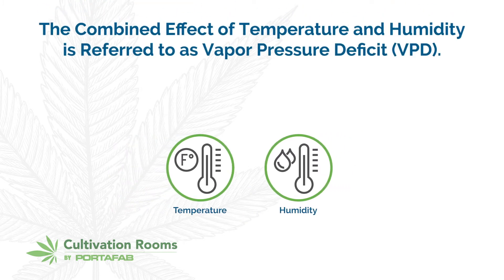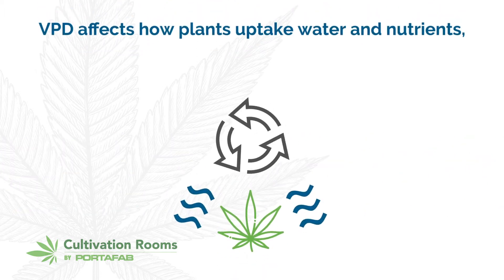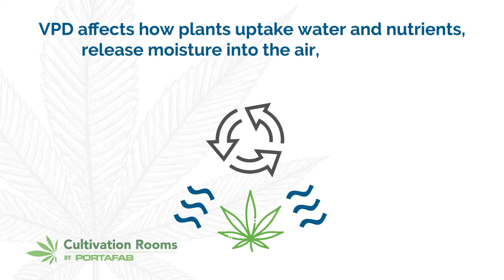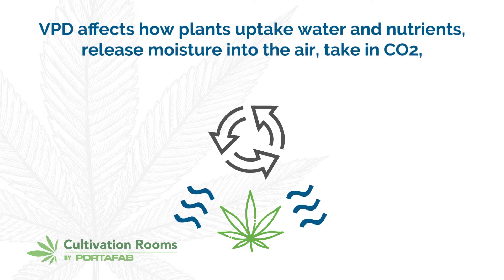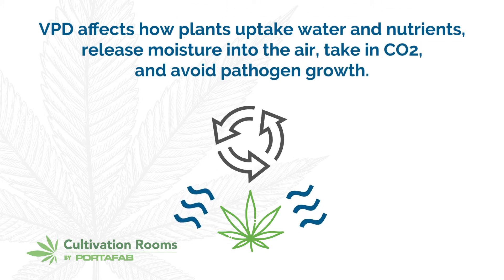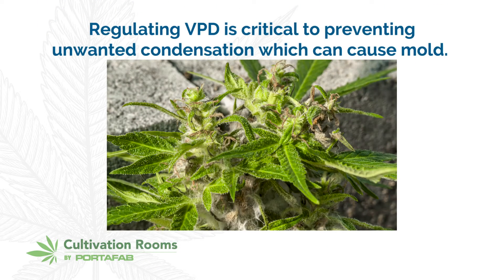The combined effect of temperature and humidity is referred to as vapor pressure deficit or VPD. VPD affects how plants uptake water and nutrients, release moisture into the air, take in CO2, and avoid pathogen growth. Regulating VPD is critical to preventing unwanted condensation which can cause mold.